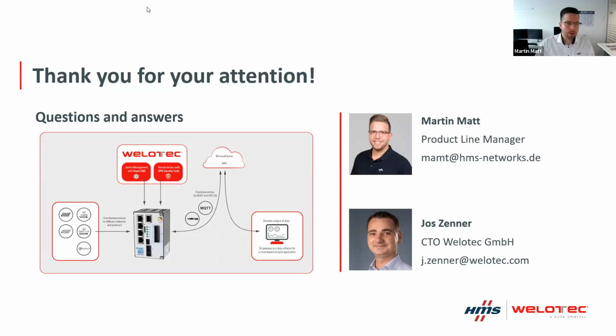That's a good question. The protocols are not always available in every device, since we have hardware and software variants. Software protocols like 61850, 104, Modbus TCP, and Modbus RTU are pretty much always available. But for hardware connectivity, you must decide: if you want to connect to a Profinet device, then Ethernet IP and Profibus won't be available. If you want GPIOs, then the industrial protocols aren't available. So we have different variants, and this is pretty much on a per-order basis. We have a lot of combinations, but not all protocols at the same time are possible, unfortunately, due to hardware limitations.